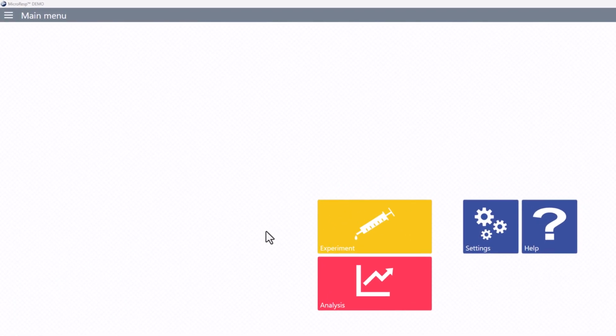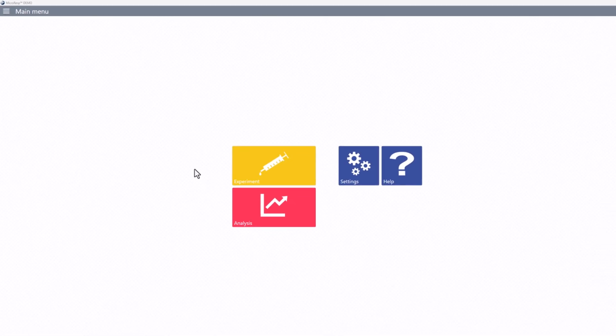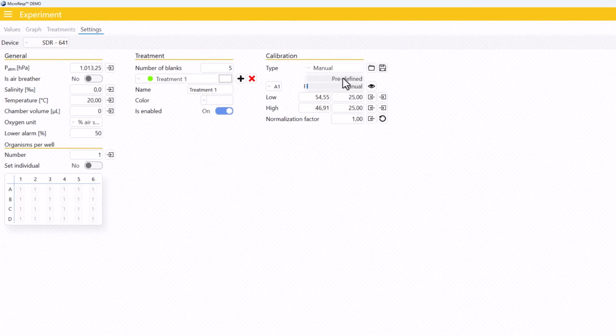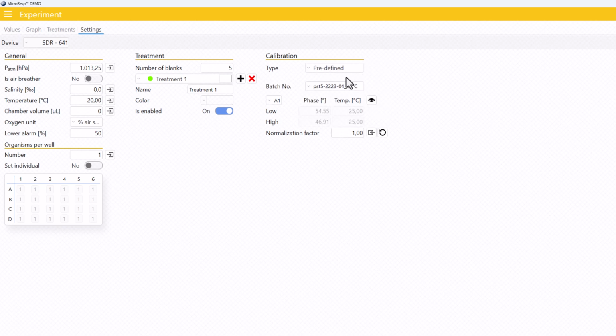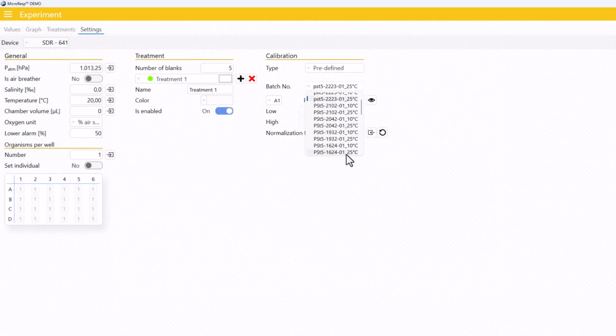Note that we are running in demo mode, so the microplate data you see here is virtual data. In the Settings menu, under the Calibration section, you can choose between two types of calibrations: factory or batch calibration and a manual 2-point calibration. The predefined or factory batch calibration uses a batch file containing the factory calibration data from back when the sensor spots were manufactured. The specific batch file number is located on the black plastic bag that the glass plate arrived in, and the file can be chosen from this list.